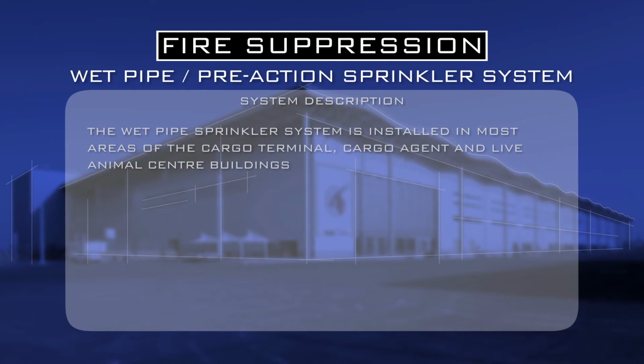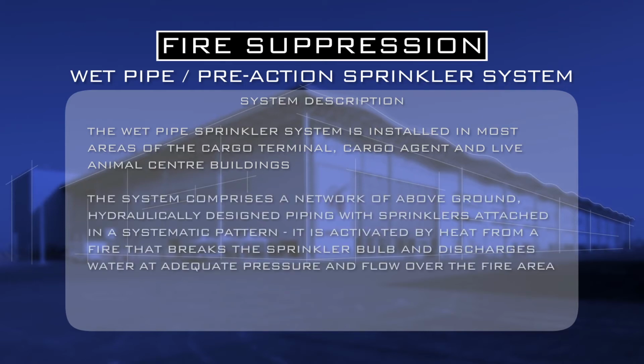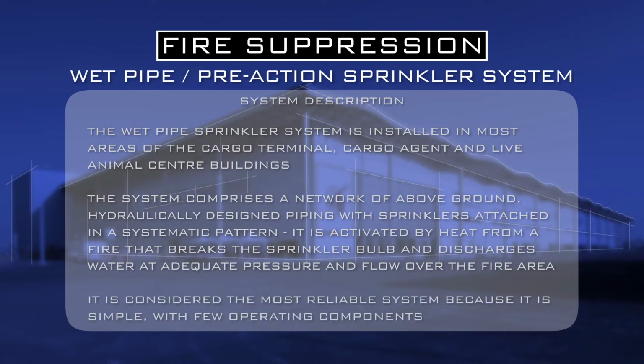The wet pipe sprinkler system is installed in most areas of the cargo terminal, cargo agent, and live animal centre buildings. The system comprises a network of above-ground hydraulically designed piping with sprinklers attached in a systematic pattern. It's activated by heat from a fire that breaks the sprinkler bulb and discharges water over the fire. It's considered the most reliable system because it's simple with few operating components.